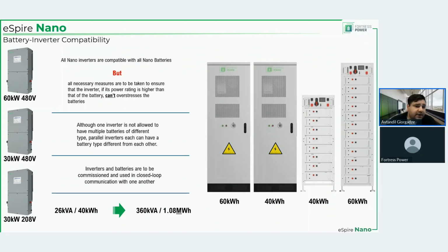Then, although one inverter is not allowed to have multiple batteries of different types, parallel inverters can each have a battery type different from one another. So what this means is that, let's say you have one 30 kilowatt inverter, which is rated at 480 volts, and another identical inverter working in parallel with this first one. As I said in one of the previous examples, one inverter can have a 60 kilowatt hour battery unit. The other one can have two 40 kilowatt hour units. Or, for example, one inverter can have one 60 kilowatt hour unit. The other inverter can have two 60 kilowatt hour units. What is not allowed is mixing within one inverter. One inverter can have whatever battery it has, 40 kilowatt hour, 60 kilowatt hour, or 240 kilowatt hours. But you may never have 40 kilowatt hour and 60 kilowatt hour units mixed and connected to one inverter. That is not allowed.